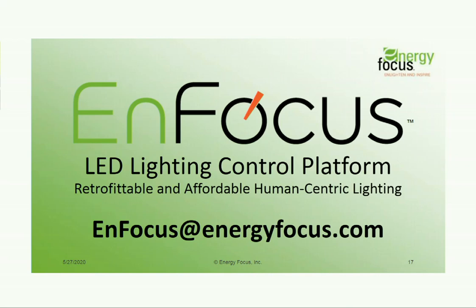0 to 10 volt systems require extra wires. So you can use a non-proprietary system if you're willing to, for example, have extra wires. But unless they're already installed in a building, they're very difficult to add, which is why many 0 to 10 volt fixtures that have been installed are never dimmed. The wires to dim them just aren't there. EnFocus doesn't require any additional control wires. It works with the existing wiring. It took a new protocol, let's say, to make that happen. So maybe we'll become the new standard. Who knows? Good. I hope so.